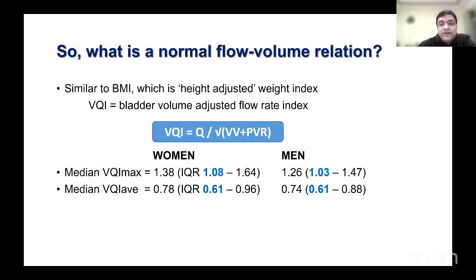So we found these values in men and women, as written here. In general, if you have a VQI max of more than 1 in either a man or a woman, or a VQI average of more than 0.6, that is 60% of the Qmax, it is considered to be acceptable flow. Just changing it into some practical parameters: for a 300 ml void, a Qmax of 18 plus is acceptable because this VQI max is around 1. And a Q average of more than 10 is good enough because the VQI average is 0.6. However, the ideal value would be more than 22 and 14.